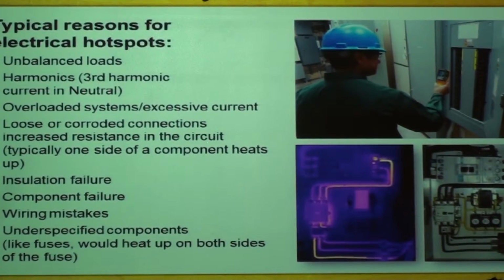If you have too much harmonics, especially third harmonics. Third harmonic is such that it always adds up on the neutral feeder. So when you make a measurement, and you get very strange current readings on the neutral, that's definitely third harmonic. So with thermal imaging, I make a measurement on my cabling, and I see the neutral feeder extremely warm, warmer than the phases, which should not happen. That's a sign telling me, hey, I've got a lot of third harmonics there. Unbalanced loads, also a very common cause of electrical hotspots. Overloaded systems, too much current, again, remember the formula, I squared R. Too much current, more heat.